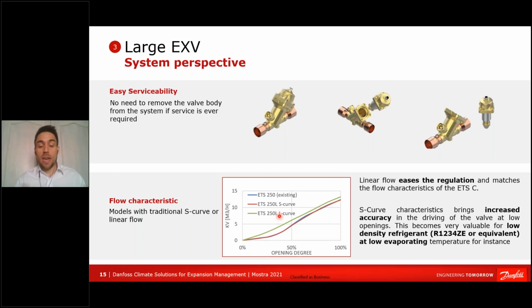Some of our customers liked it because when you are quite closed, at a very low opening degree, you have very accurate precision, meaning with some steps you have very little opening of the valve, so the KV is moving slowly. That could be very beneficial when you're working at low evaporating temperature with fluids such as ZE. You need to be very accurate when you're approaching low pressure. For those kinds of applications, for instance a heat pump working with ZE at very low evaporating temperature, that improved accuracy with the valve might be very beneficial. So that S-shaped curve could be a very significant value proposition for many applications that are looking for accuracy when the valve is quite closed.